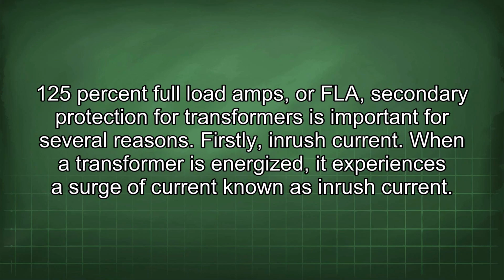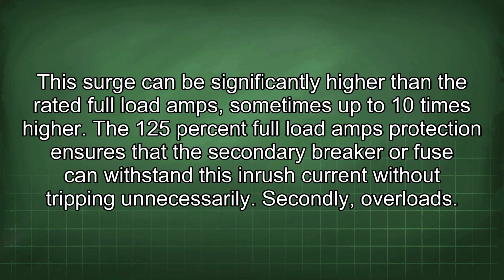125% full load amps, or FLA, secondary protection for transformers is important for several reasons. Firstly, inrush current. When a transformer is energized, it experiences a surge of current known as inrush current. This surge can be significantly higher than the rated full load amps, sometimes up to 10 times higher.